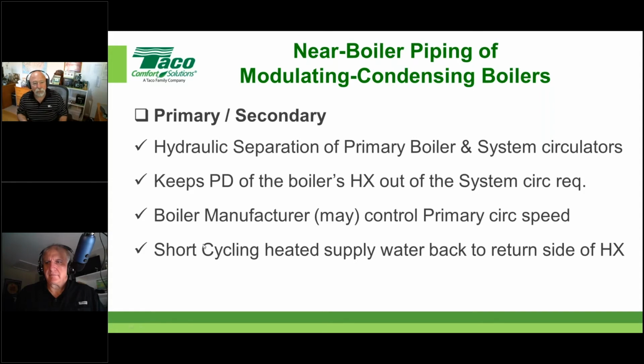Okay, if we don't get the circulator sizing correctly, it could lead to short cycling of the boiler. That's meaning the boiler's coming up to temperature quicker than it should, and it actually shuts off. Remember, we want nice long on times and long off times, and we do that by getting the boiler to come on and stay on and not limit on its high limit. So we're going to get into this. We're going to touch on this bullet quite a bit and show you how to avoid that as best as you can.